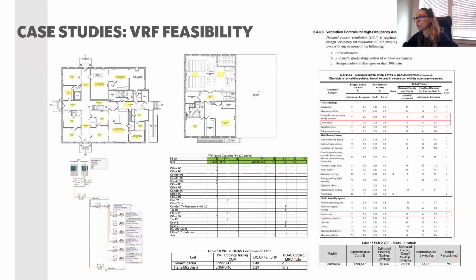And so we looked at the code for the minimum ventilation rates, and we came up with a preliminary design for them, which also includes all the controls. And we showed them the implementation cost, a ballpark, what it's going to be, and what the simple payback is. Because the VRF system is a very efficient system, we were actually showing almost 50% energy savings, even though the implementation cost is really high. It was showing a 29-year payback. We also recommended, in case this is too expensive and they cannot go for it, replacing the current heat pump units that are showing problems, and it was actually showing very similar payback periods. So we are trying to show various options based on the budget of the client, but this was an interesting study that I wanted to share.